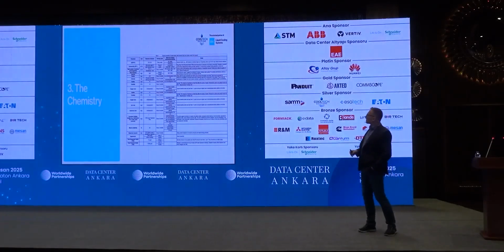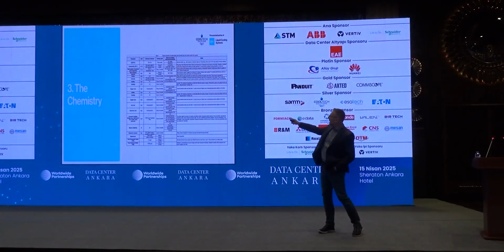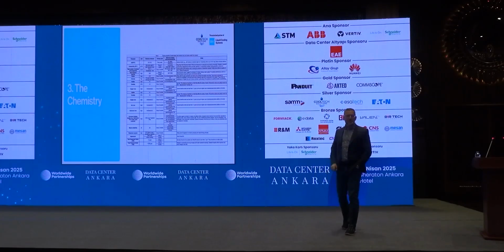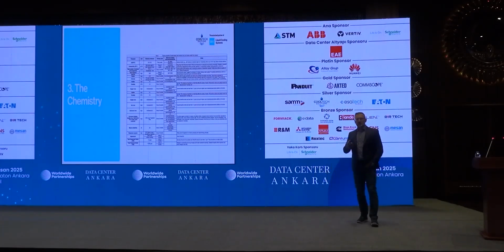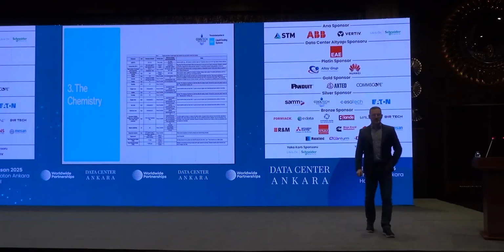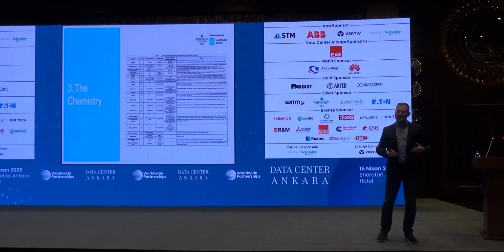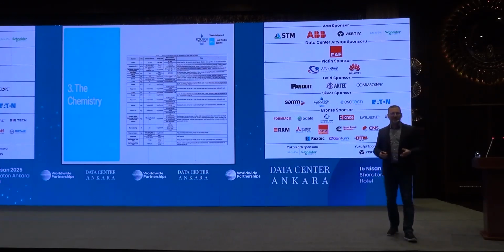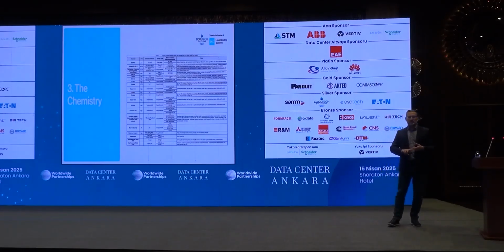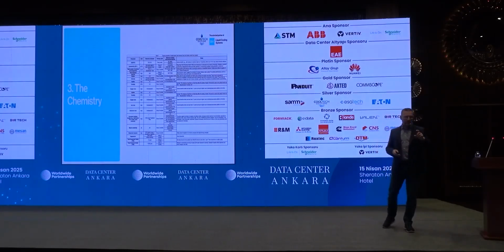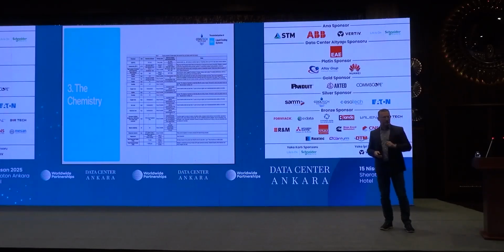And the final item - there's not much here, but there's lots of ions, turbidity, conductivity, pH, corrosion rate, all those parameters of water. The chemistry and the right maintenance schedule is the most important part in every single direct cooling system. As you can imagine, warm water is a perfect place for growth of bacteria, of fauna or flora. So we need to add additives, biocides, corrosion inhibitors, and other inhibitors. You need to control the cooling medium - that's water, DI water, or any mixture.